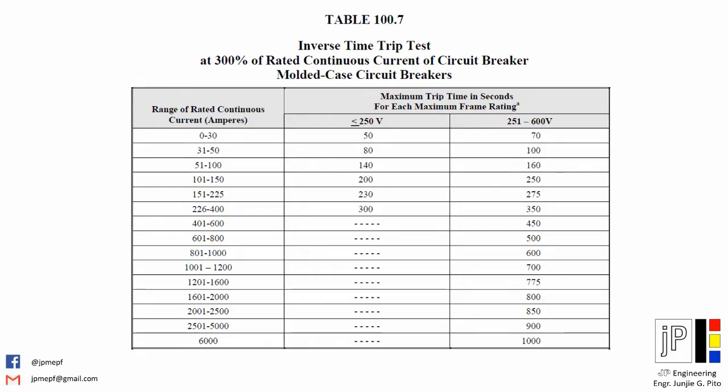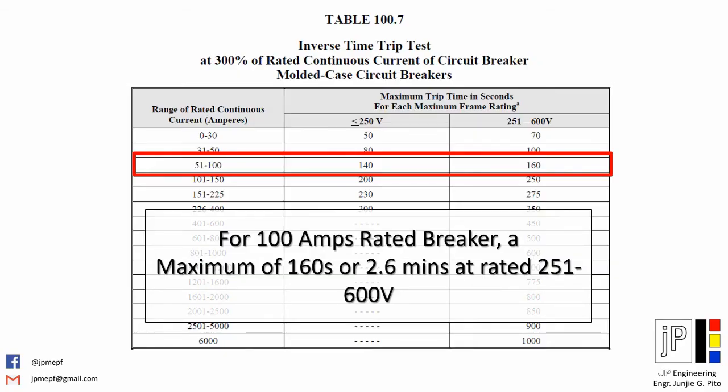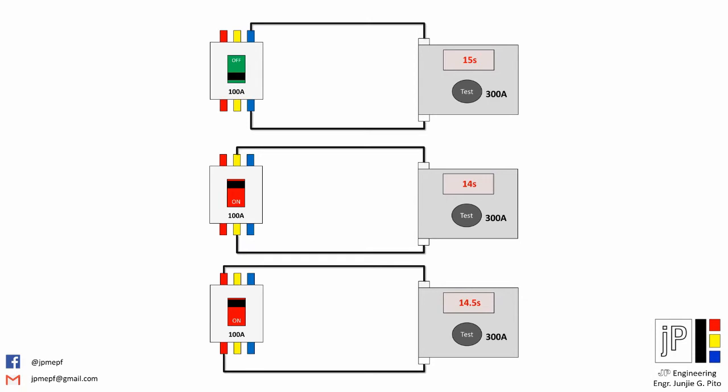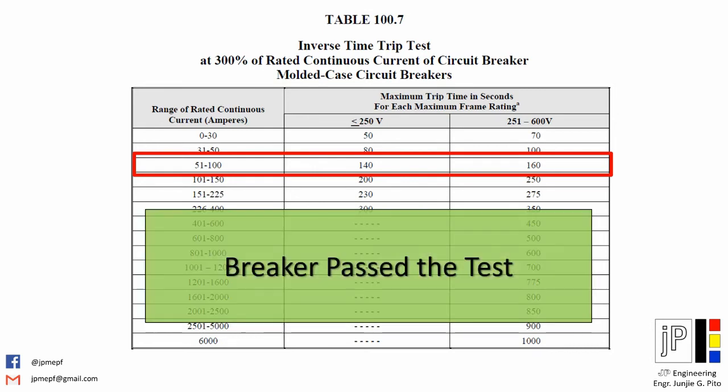As per ANSI standard on Table 100.7, a circuit breaker with a rating of 51 to 100 amps and a nominal voltage of 251 to 600 volts shall have a maximum tripping time of 160 seconds, which is about 2.6 minutes. Our sample test recorded a trip within 14 to 15 seconds, and therefore the subject breaker passed the trip test.